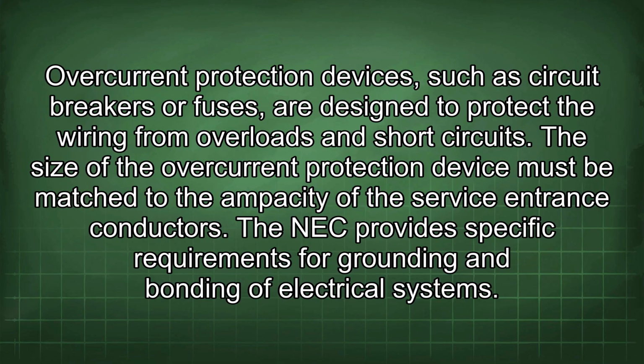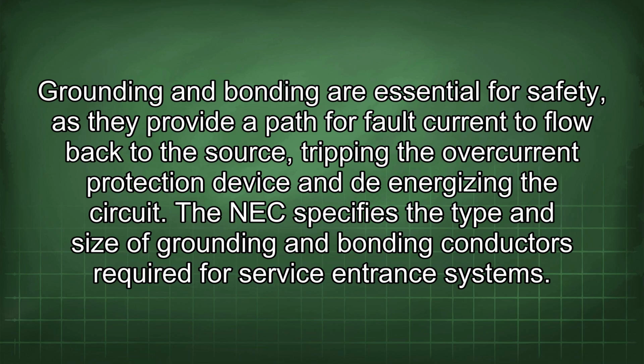The NEC provides specific requirements for grounding and bonding of electrical systems. Grounding and bonding are essential for safety, as they provide a path for fault current to flow back to the source, tripping the overcurrent protection device and de-energizing the circuit. The NEC specifies the type and size of grounding and bonding conductors required for service entrance systems.